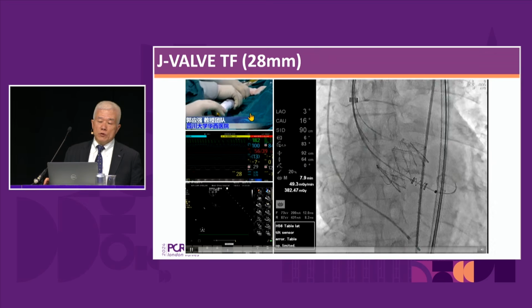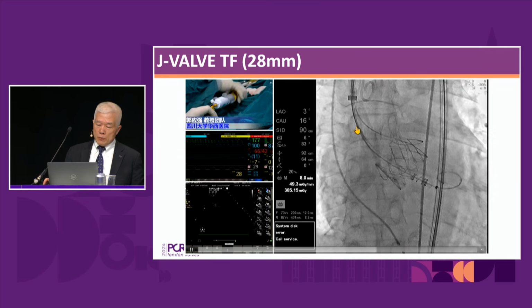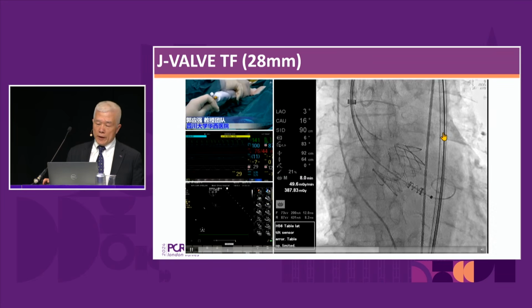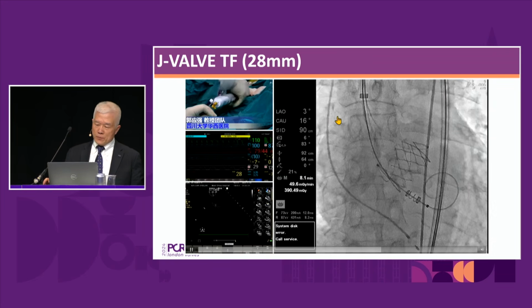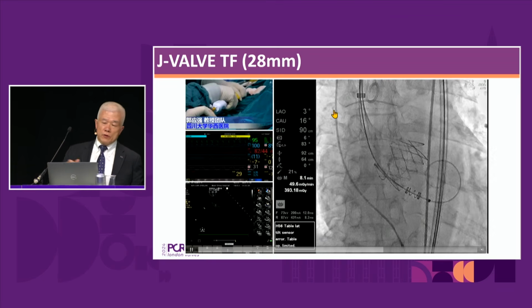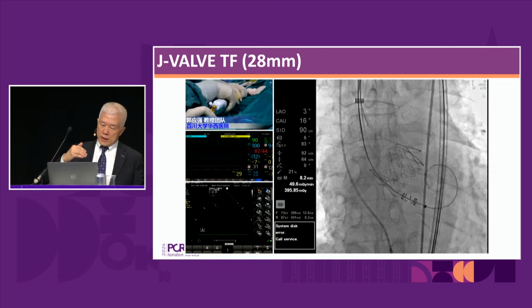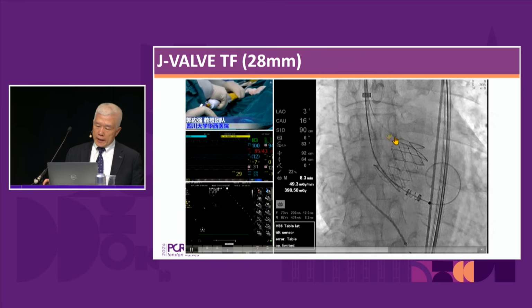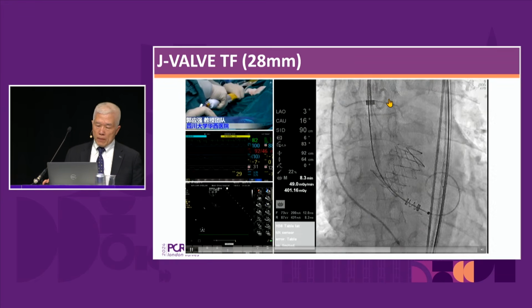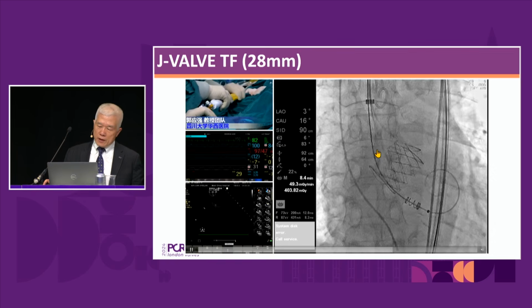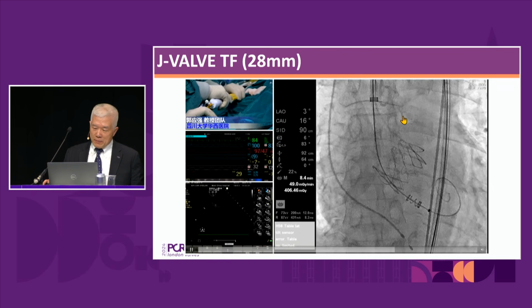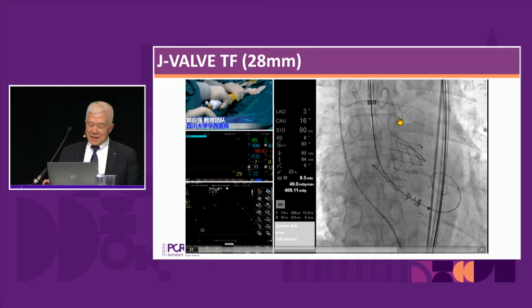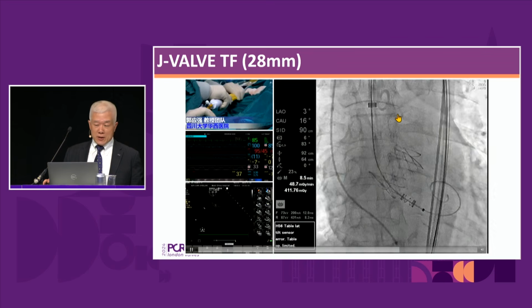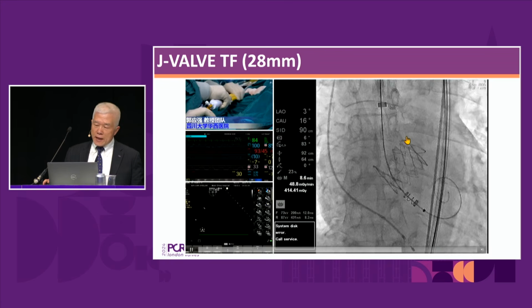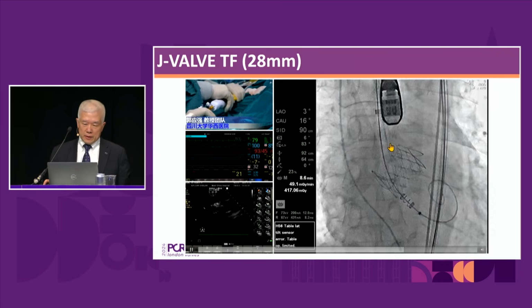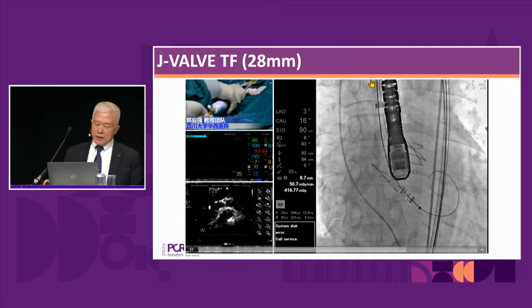And then you can see if you release the yellow knob, which controls the U-shape anchor ring, and then just turn a half turn, and then it's released. Now follow the sequence: move the yellow and the gray together to withdraw the connection cable. The connection cable is falling down. Apologies, because I'm looking very clearly. So definitely you need to be cautious. Sometimes you need to really carefully detach the U-shape anchor ring. But now all three connection cables are detached.